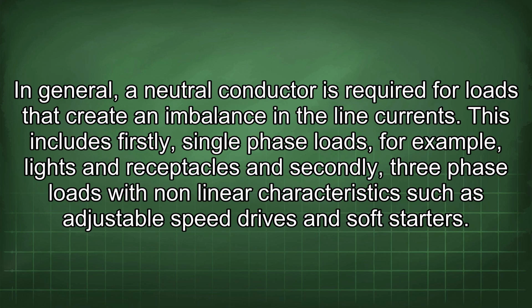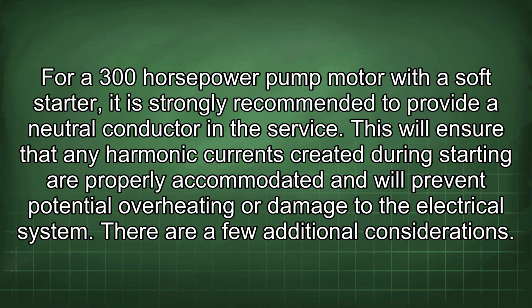In general, a neutral conductor is required for loads that create an imbalance in the line currents. This includes, firstly, single-phase loads, for example, lights and receptacles, and secondly, three-phase loads with nonlinear characteristics such as adjustable speed drives and soft starters. For a 300 horsepower pump motor with a soft starter, it is strongly recommended to provide a neutral conductor in the service. This will ensure that any harmonic currents created during starting are properly accommodated and will prevent potential overheating or damage to the electrical system.